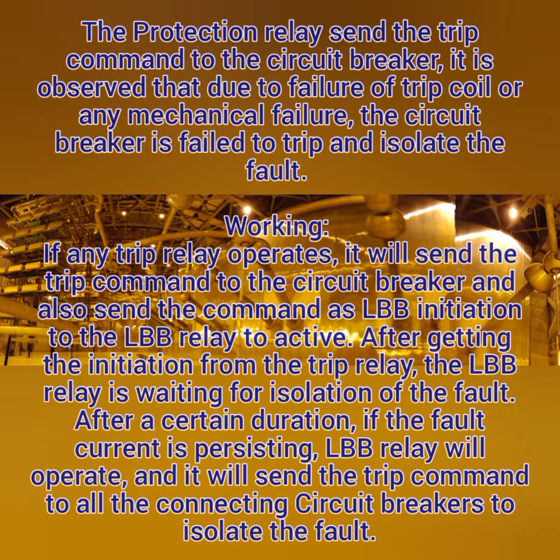If any trip relay operates, it sends the trip command to the circuit breaker and also sends the command for LBB initiation to the LBB relay to activate. After getting the initiation from the trip relay, the relay waits for isolation of your fault.